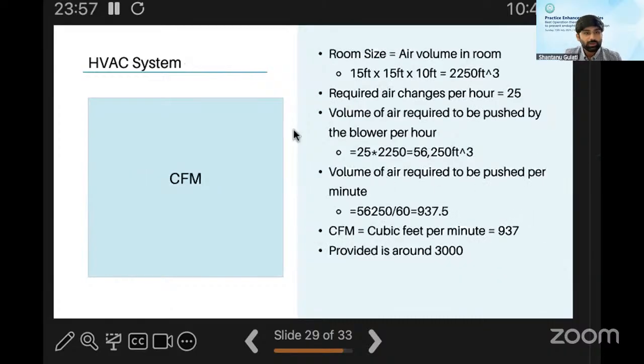So I would just like to talk a moment about the CFM. If the room size of your OT is, suppose, 15 feet by 15 feet and 10 feet height, that makes the volume of air inside your room around 2300 cubic feet. And if there are 25 air changes required per hour, that means your AHU has to push 25 times that volume, which is around 57,000 cubic feet. So the volume of air that has to be pushed per minute means you divide this value by 60 and you get the CFM. What you'll see is that the required CFM is around 1000, but generally the vendors are providing 2 to 3 times this capacity for the AHU. So this is what the CFM means when your vendor talks about it.